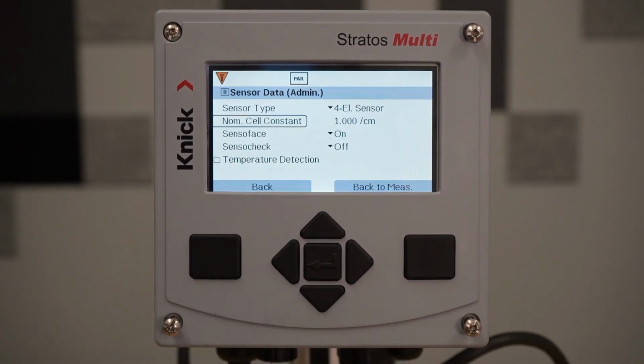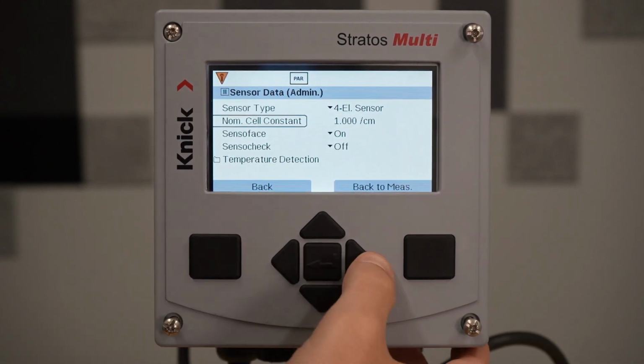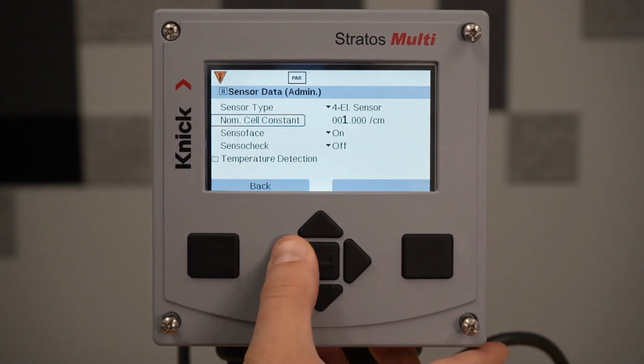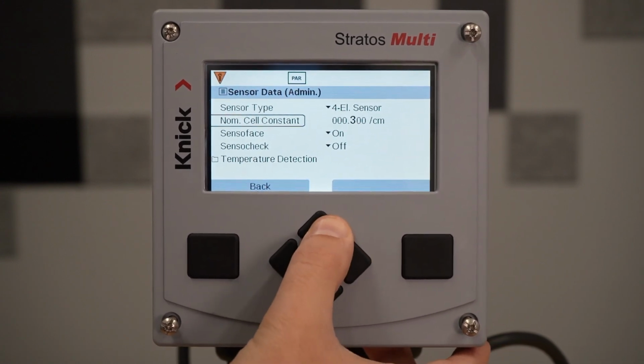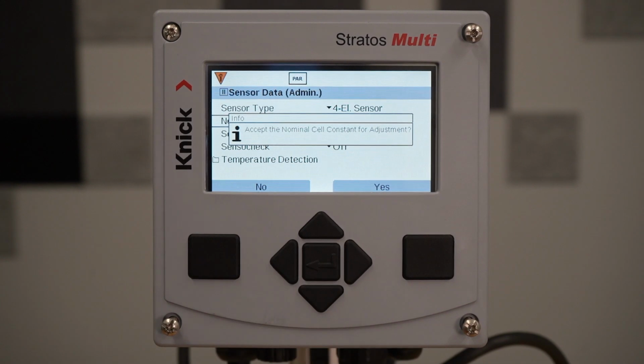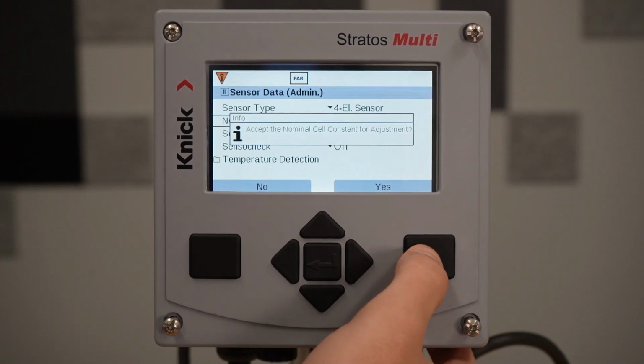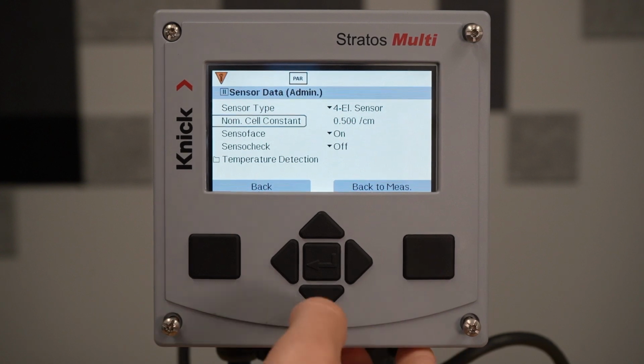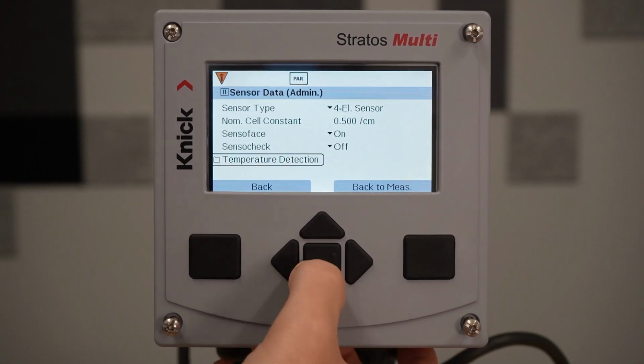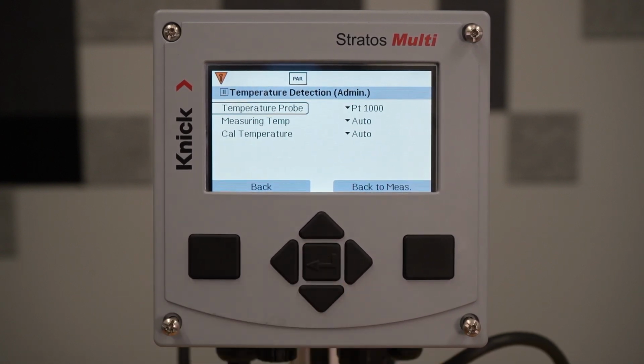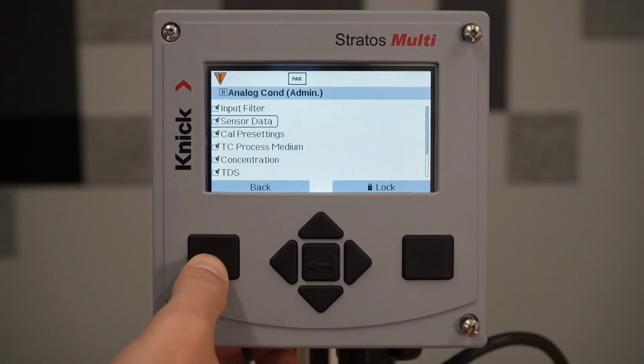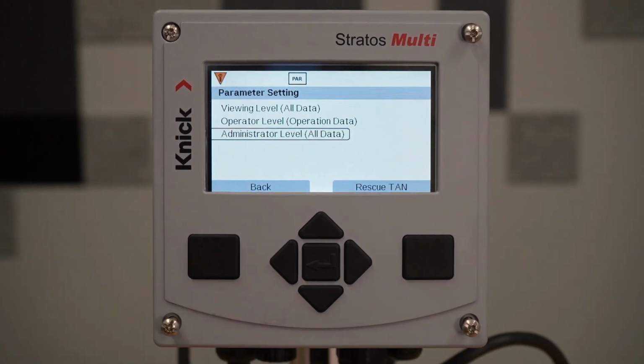Additionally, the nominal cell constant for the K25 is going to be 0.5 per centimeter. We will accept the nominal cell constant adjustment here. And then additionally, we will go down into temperature detection and make sure that we are set for PT 1000. Once this is all set up, we can go through a calibration of our sensor, which will be shown in a separate video.